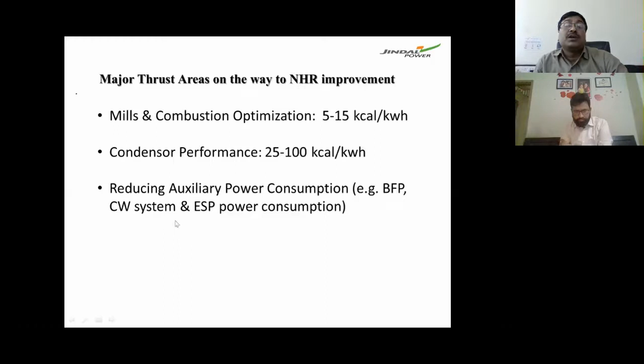I have depicted the financial effect of only a 0.1% APC saving. If we consider our station APC as 6.94% and we improve by 0.1% only, to 6.84%, if annual generation is 21,024 million units, that 0.1% APC saving accounts to 21 million units of extra export. So annual savings, considering 3 rupees per kilowatt hour, will be 631 lakh rupees. That is 6.31 crore rupees.